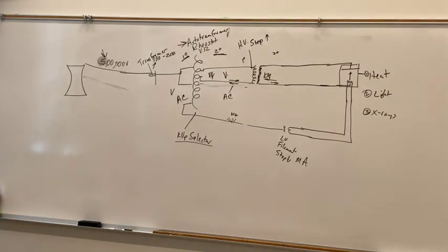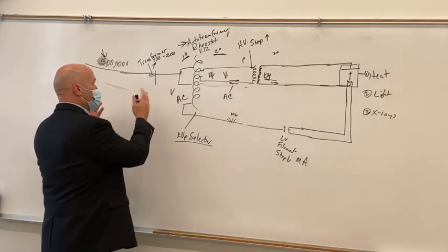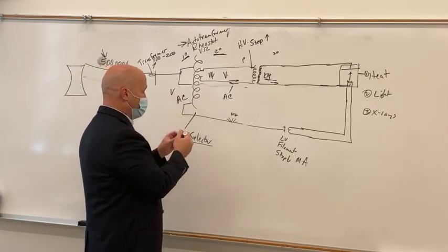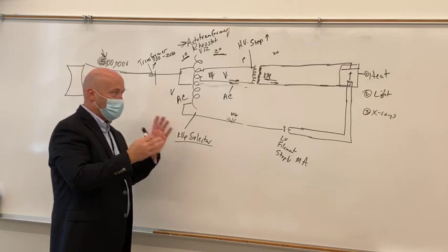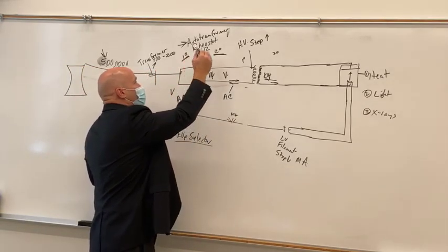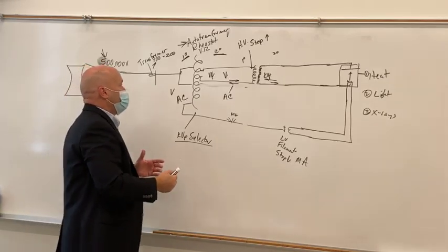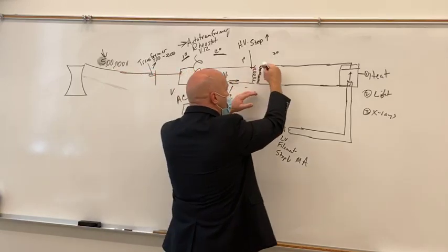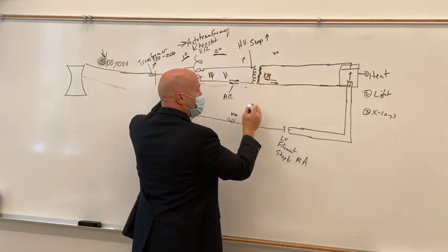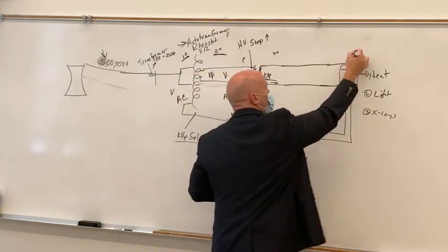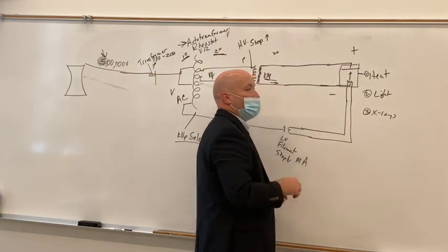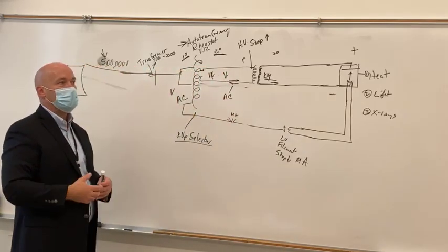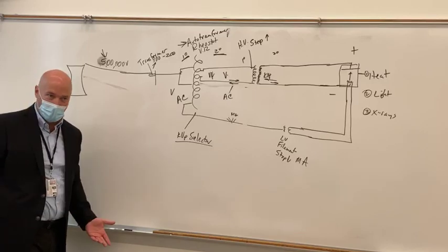So the primary function of the imaging system is to do just that, to take electricity that we're supplied, a set amount of electricity or set voltage, power level of electricity. And there are some other things in here we're going to talk about later in the semester, but this is primarily where I want you to be right now. And we're going to manipulate that electricity to set a specific amount of electricity so that we can boost that up to a high voltage based on what we set over here, so that we can adjust the relative positive and negative charges inside of the X-ray tube, so that we can accelerate those electrons across the tube at a given rate of speed, so that we can create X-rays in the energy level that we need them to be, okay? A lot of words to say.